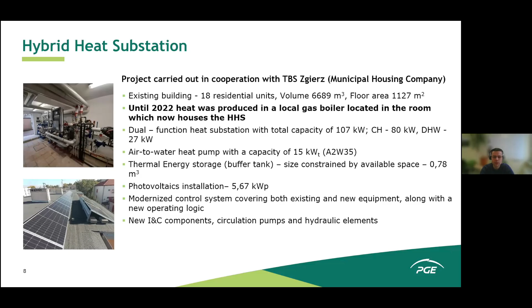The first one is the hybrid heat substation, as we called it. In an existing dual-function heat substation located in a small multifamily building, we installed a 15 kilowatt air-to-water heat pump supported by thermal energy storage and a photovoltaic installation. The result is a hybrid heat substation which can deliver heat from the district heating network or the heat pump, individually by one of these sources or simultaneously, depending on external conditions and automated decisions such as external temperature, etc.